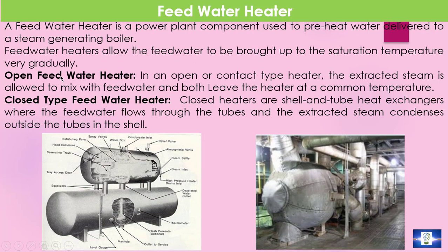An open heat exchanger is one in which extracted steam is allowed to mix with the feed water and both leave the heater at a common temperature. The advantages of the open heaters are simplicity, lower cost and high heat transfer capacity, and the disadvantage is the necessity of a pump at each heater to handle the large feed water stream.